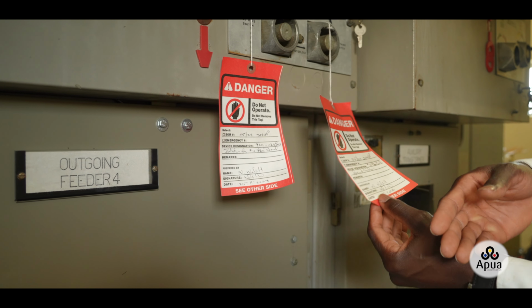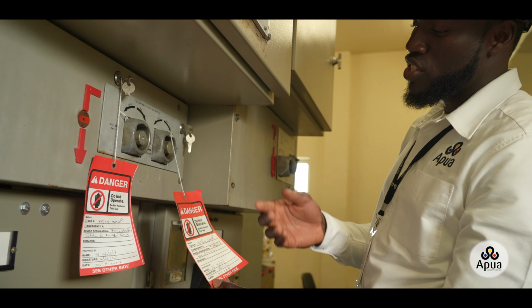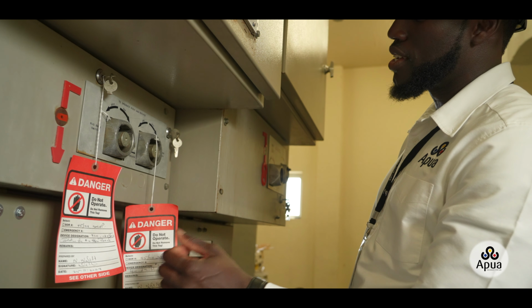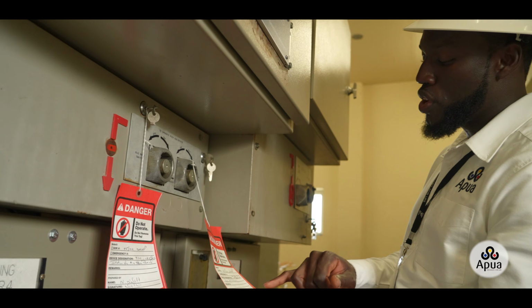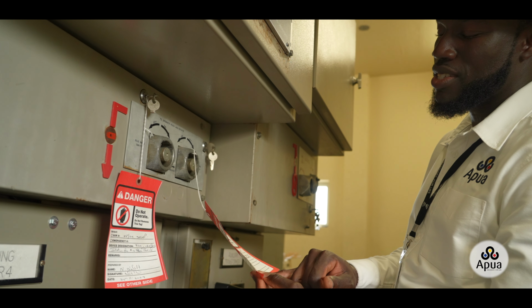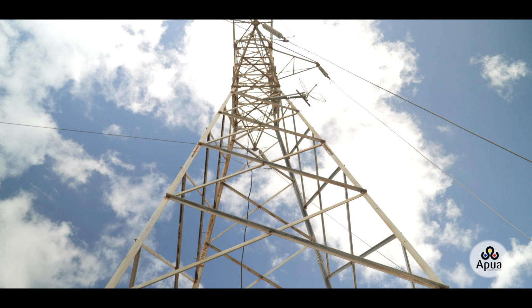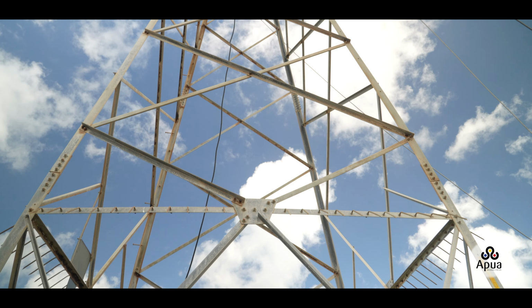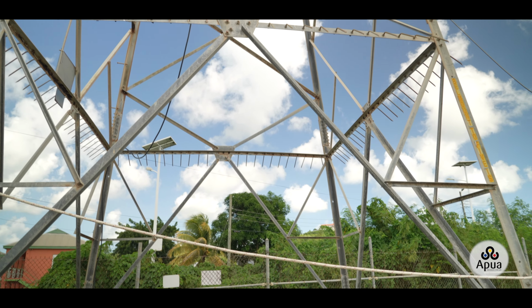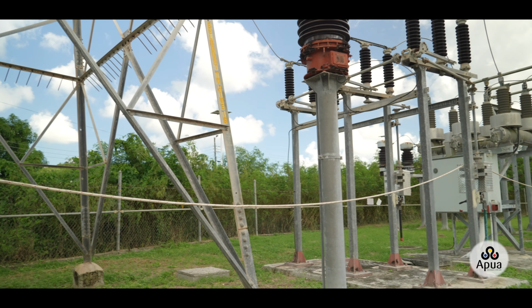During the oil reclamation process, we have to de-energize the substation for the period. It lasts about 10 days, but we're quite flexible. We can connect those customers that are normally fed from that substation to other substations, so customers would not have extended outages. The outage that they would experience is just to switch from one substation to the next, which is probably 15 minutes. So we don't anticipate customers to be out of service for any extended time.